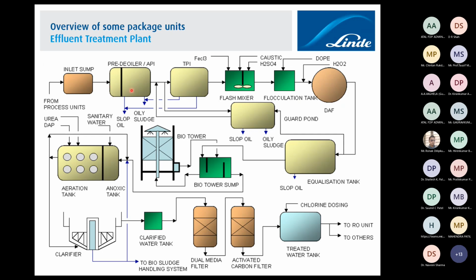And basically the API or TPI is usually meant to take care of larger oil amounts, from 2% oil down to 250 ppm, parts per million. So 1% means 10,000 ppm, and 2% means 20,000 ppm. So 20,000 ppm to 250 ppm oil removal is happening in the pre-deoiler and TPI unit, and the DAF further reduces it to 10 ppm. When it is below 10 ppm, you cannot visualize it with the naked eye. Sometimes on the surface, in the presence of sunlight, you will see some coloration difference. So this is the purity you can achieve at the end of the pre-treatment area or oil treatment area.